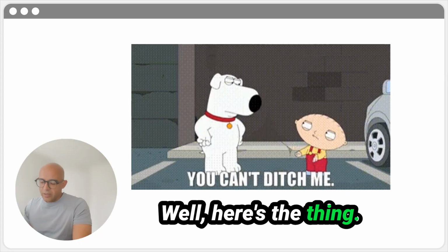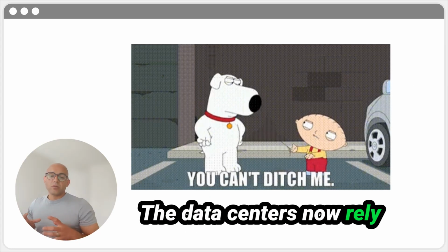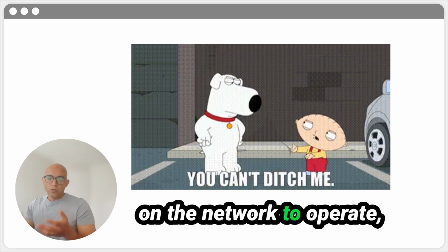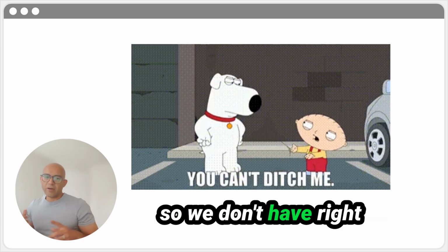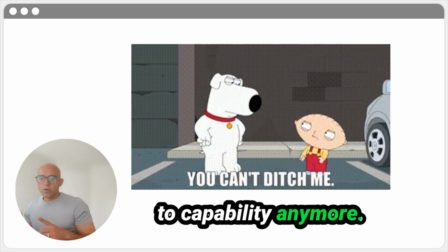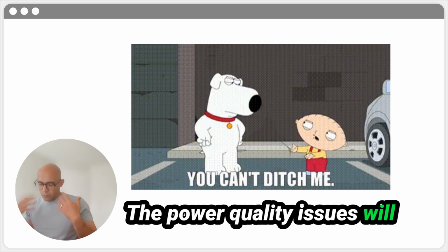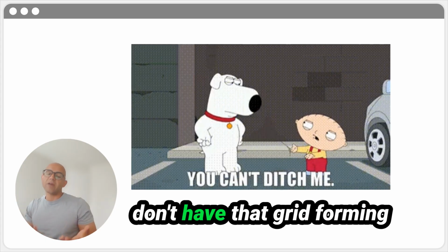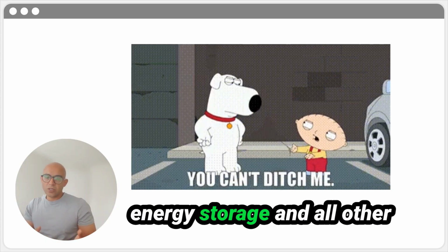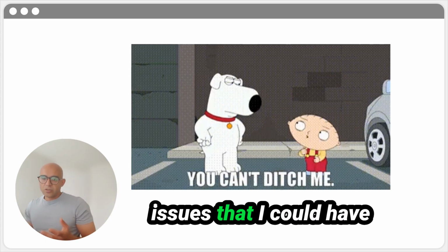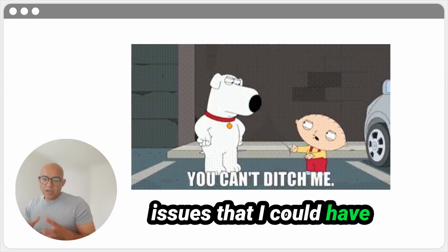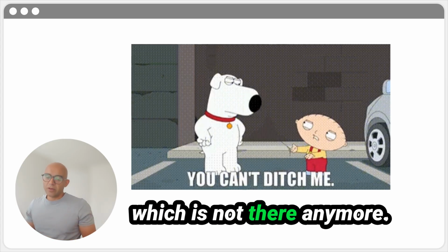Well, here's the thing. The data centers now rely on the network to operate, so we don't have ride-through capability anymore. Power quality issues will come into place because I don't have that grid-forming energy storage, and all the other issues I could have resolved with energy storage are no longer addressed.